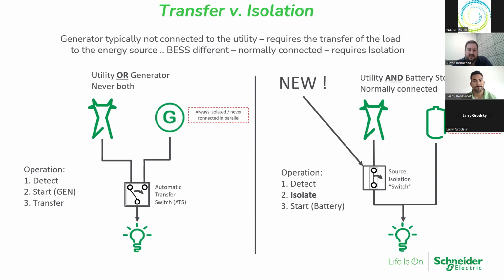And well, part of the big value prop behind an inverter is you want to do energy cost optimization, and you won't be able to backsell because the inverter is basically disconnected from everything else on the system. So you can't put it on the generator side of an ATS. Well, if you put it on the load side of the ATS, then all of a sudden power fails. You want to run on the inverter. Well, the inverter is still tied in with the utility at that point, and because you're still connected to normal, and without an emergency source, an ATS can't disconnect from the utility source. So you're stuck there, and so that's no good.